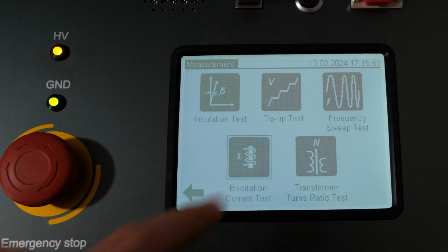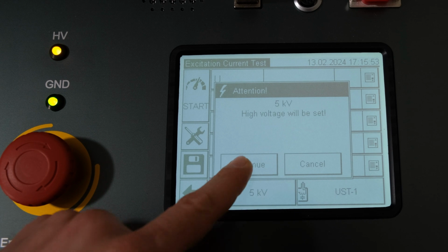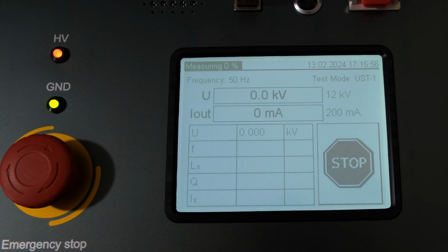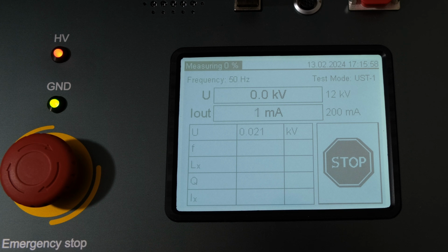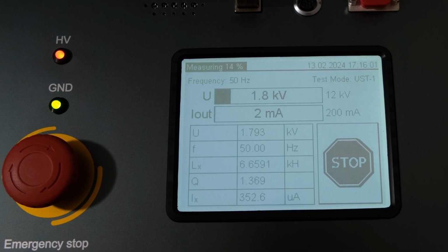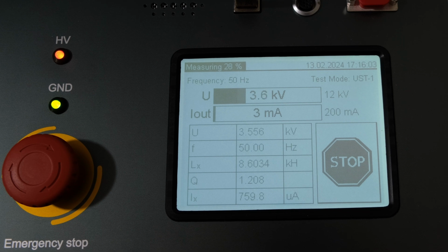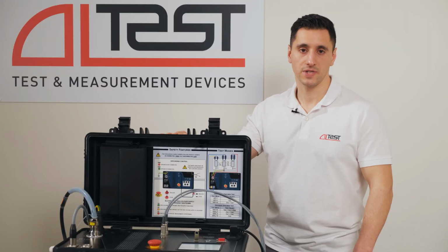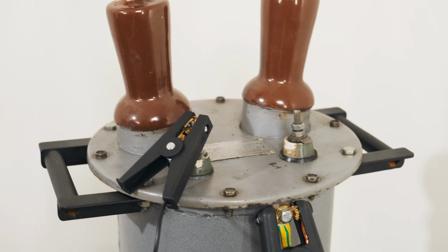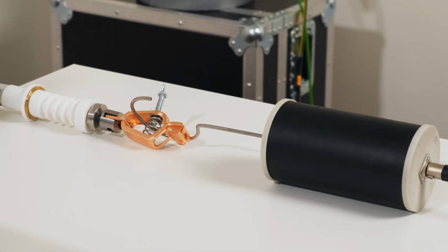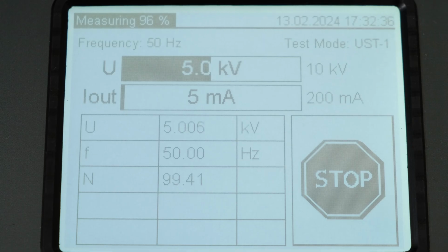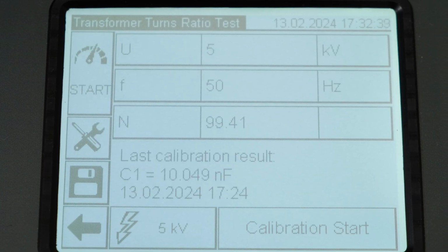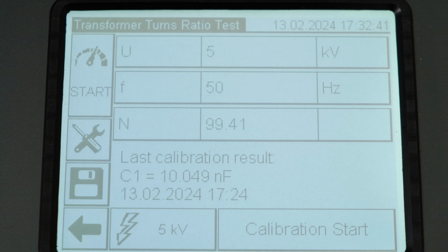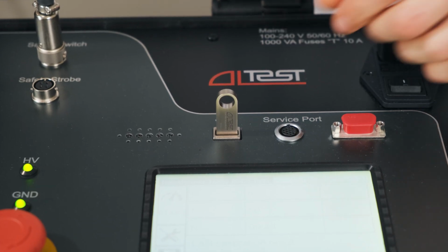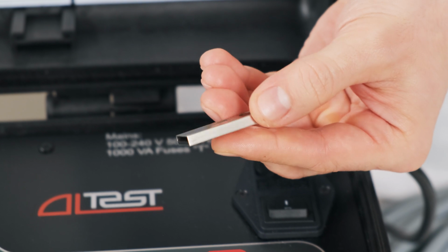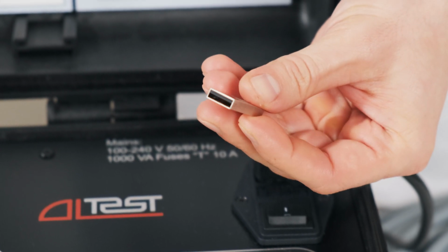In this mode, the no-load current is measured at a test voltage of up to 12 kV. The transformer turns ratio is measured in 2 stages. In the first stage, the device measures the parameters of the measuring capacitor. In the second stage, the excitation is applied to the high voltage winding. The measuring capacitor is connected to a low voltage winding. The transformer turns ratio is calculated based on the measurement results at the first and second stages. Use a built-in USB port to export measurement results to a PC using flash memory.